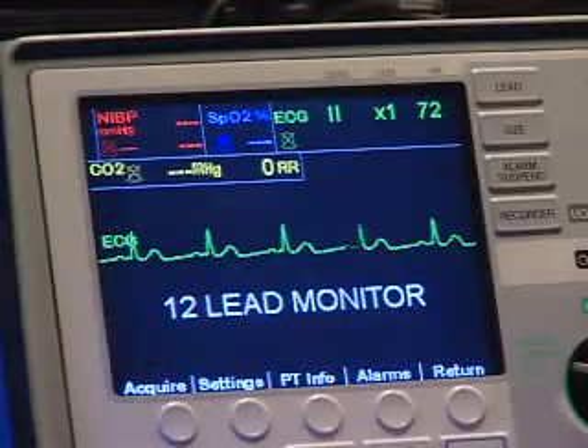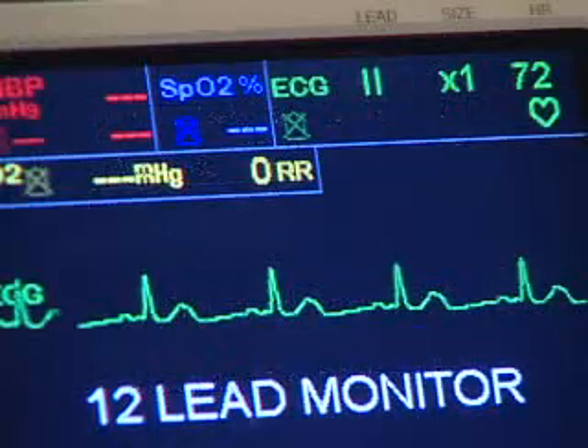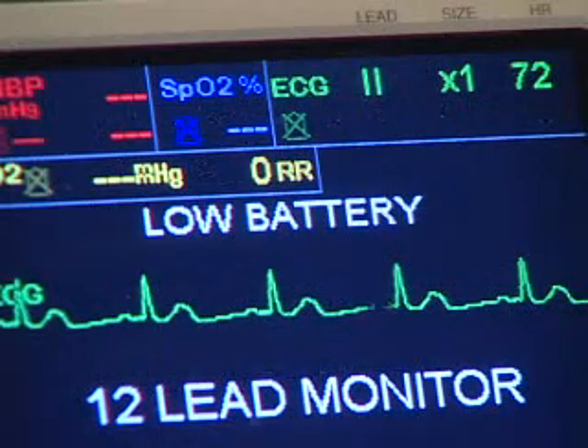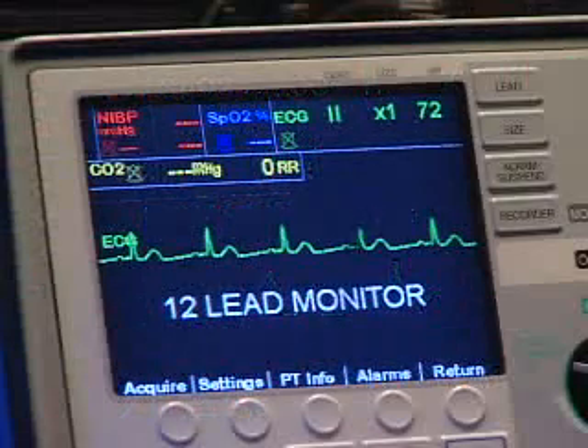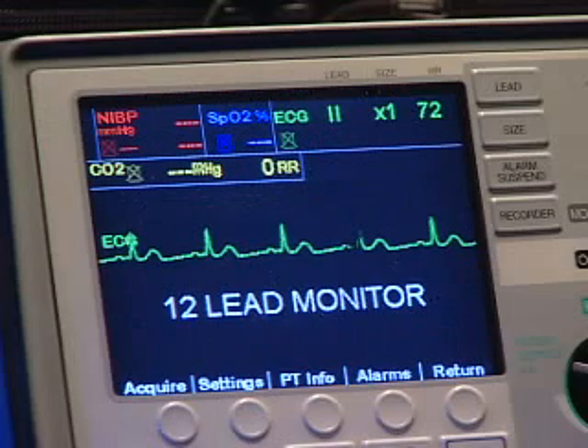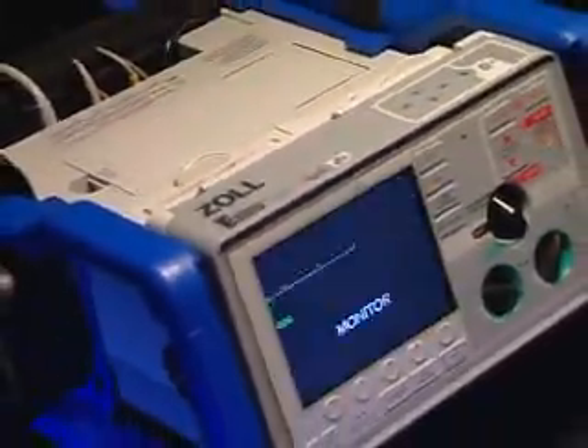When the E-Series detects a low battery condition, the low battery message is shown on the display. A 2-beep audio low battery tone is heard either once every minute or once every 5 minutes, depending on how your E-Series has been configured. As batteries age, the runtime between the low battery message and the defibrillator shutdown will decrease. It is recommended that when the low battery message warning appears, a fully charged battery pack be installed as soon as possible.